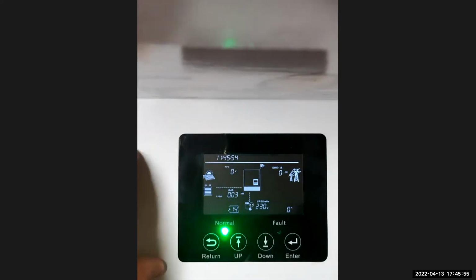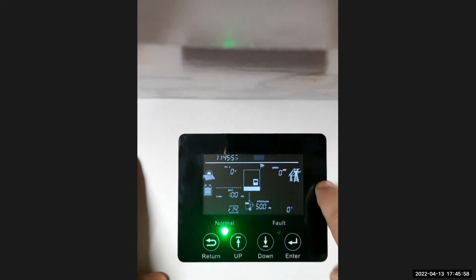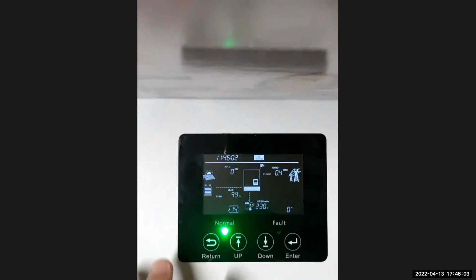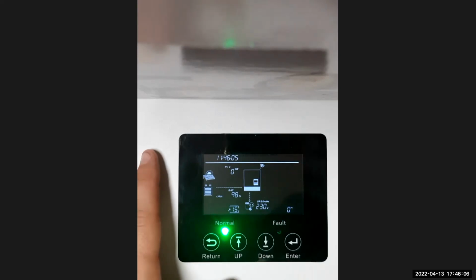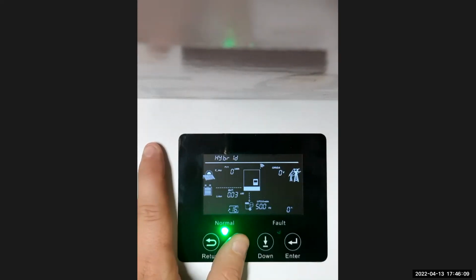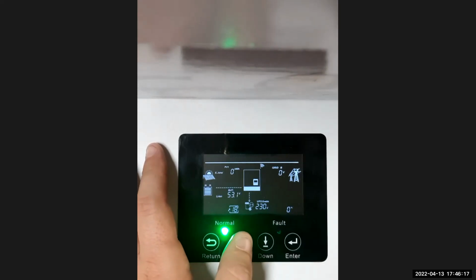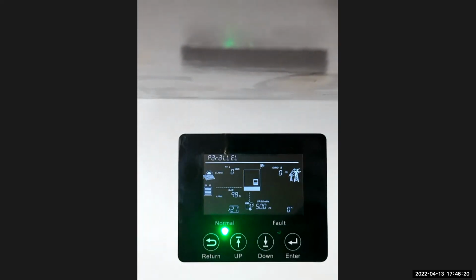Not going to use that one. Number 14 is for when you are going to have AC charge, if you would like to charge from Eskom or not. Number 14. And number 15 is for AC first. From there on, you can enable the hybrid function if you'd like, but 90% of the people don't enable the hybrid function. And then from there on, it's 21. So just to recap, it's number 3, number 6, 7, 8, 9, 10, 11, 12, 14 and 15, 16 and 21. Those are the most common settings that you have to familiarize yourself with on the screen.